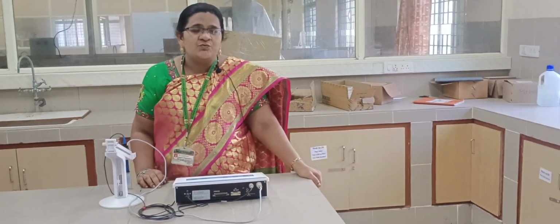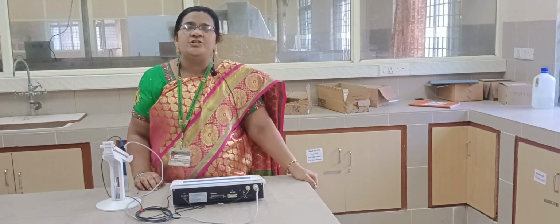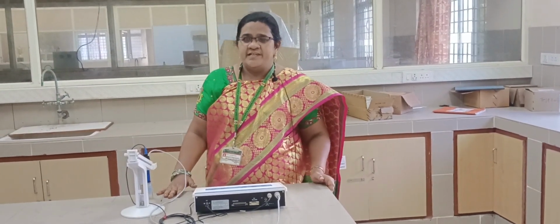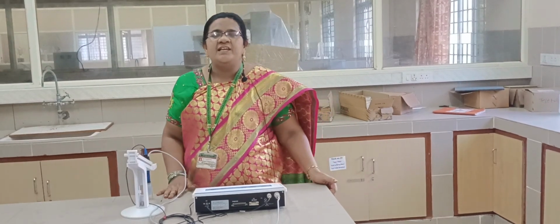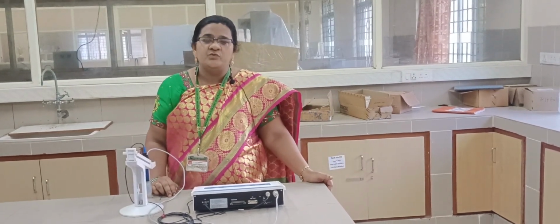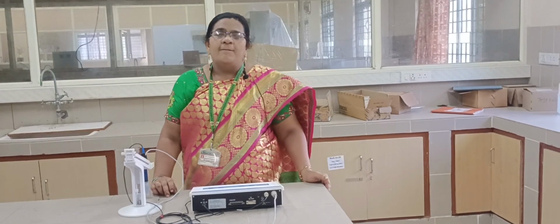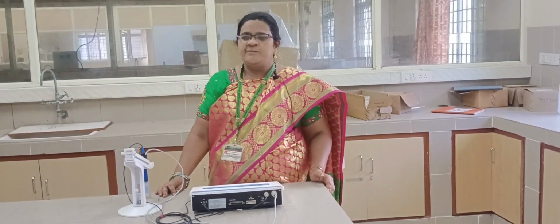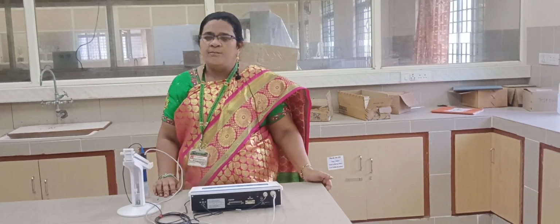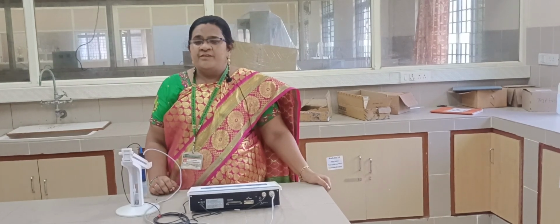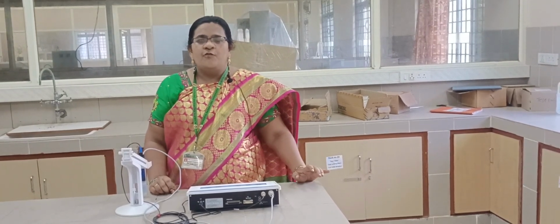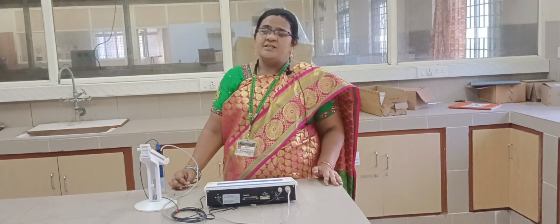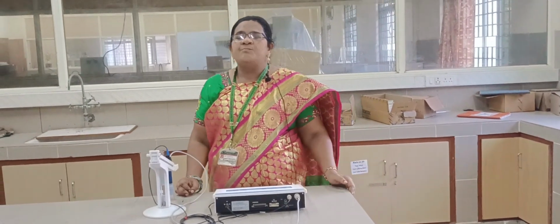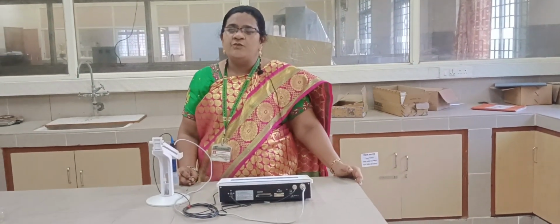Initially, the calibration was performed during installation qualification. After that, the pH meter is very sensitive, so we have to calibrate it daily when we are measuring the pH of any acid, base or biological buffers. This is used for measuring the pH of various buffers that we use in pharmaceuticals.